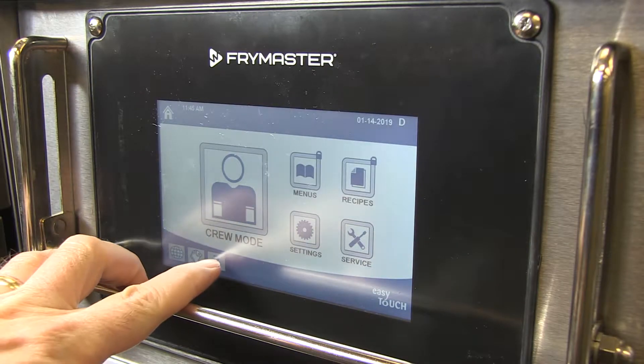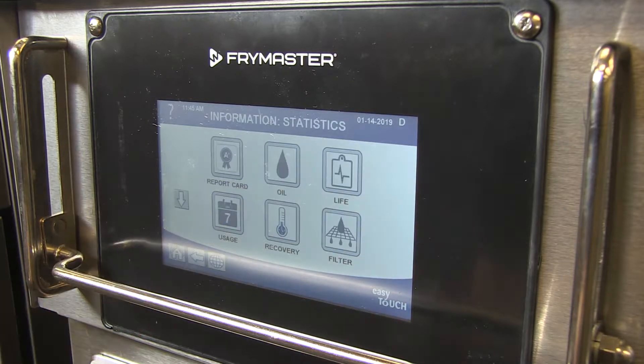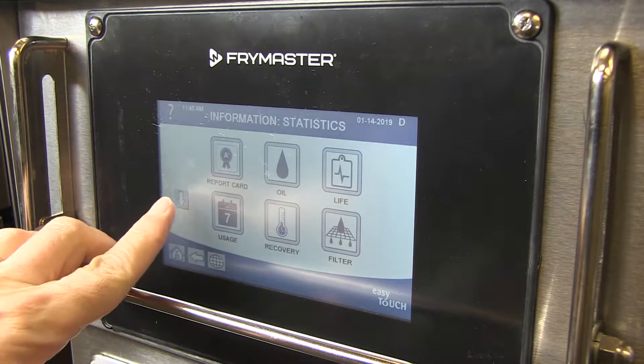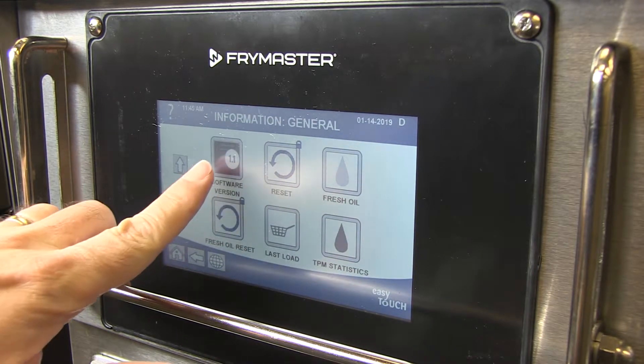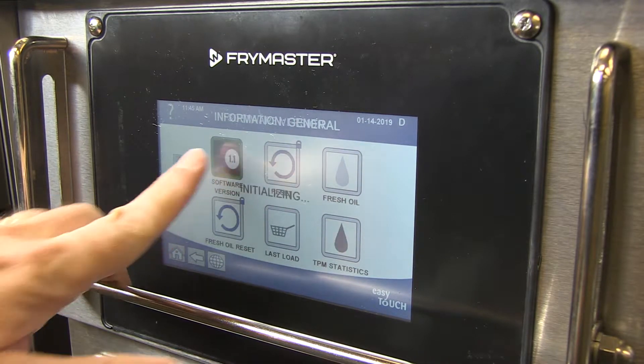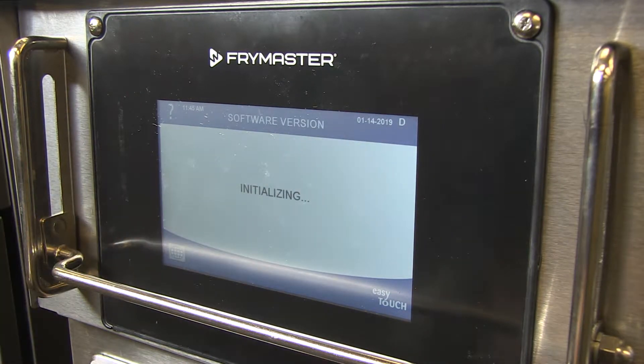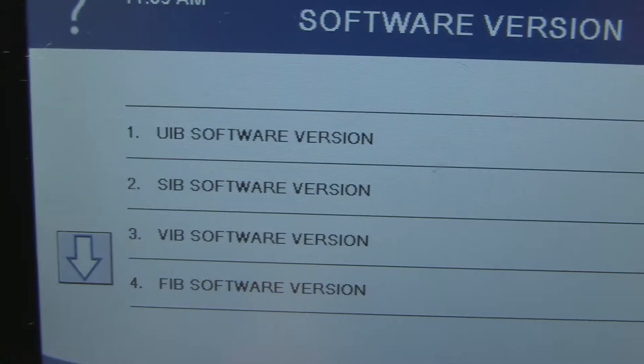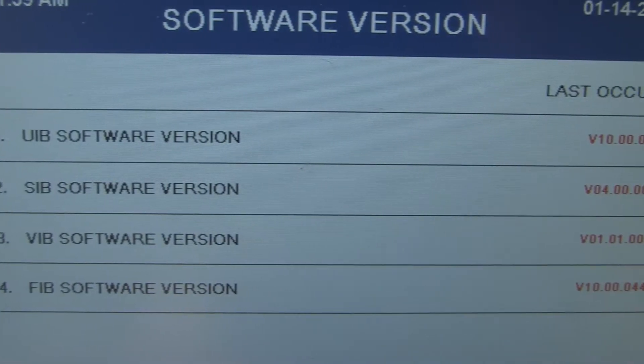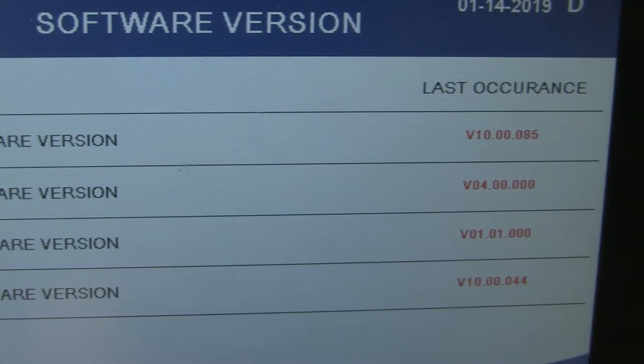Starting at the home screen on the touch screen, press the question mark icon. From there, navigate to the information screen and then the software version screen. Ensure that each board shown on the matrix has a corresponding software version number.